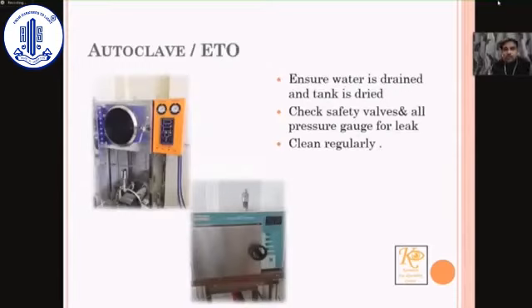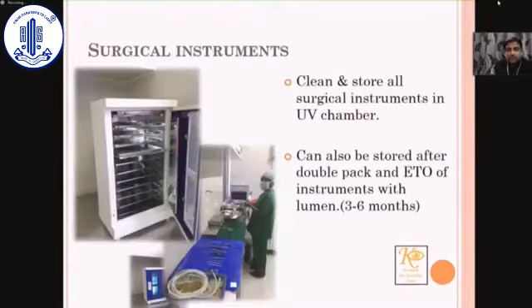The autoclave is also very important. Ensure that the water in the tank is drained and it is kept dry. Check all the safety valves, the steam inlets, and the outlets regularly. Make sure that the data in the data logger, if you have one, is already saved, because sometimes the battery goes off and you forget to change it. Better keep the chamber open to ensure that there's good aeration. In the case of an ETO or plasma sterilizer, make sure the gas cartridge is removed and disposed of properly according to biomedical waste norms.